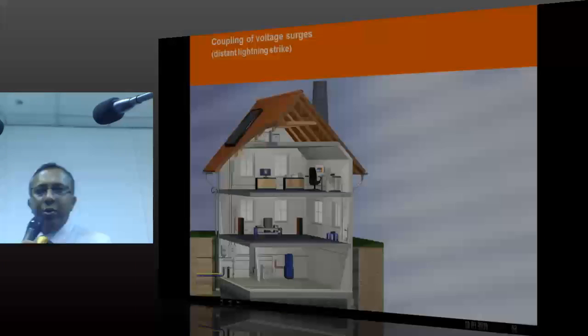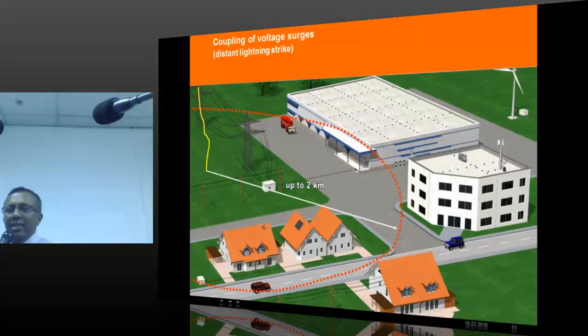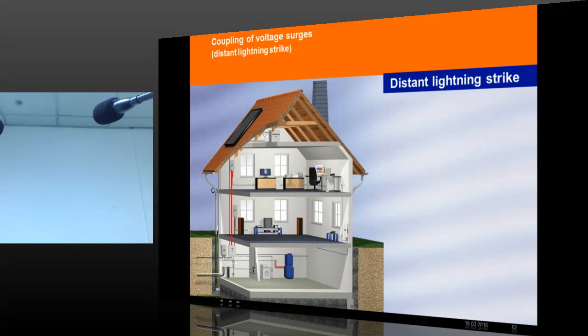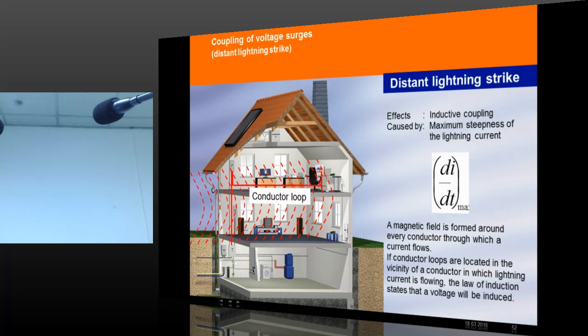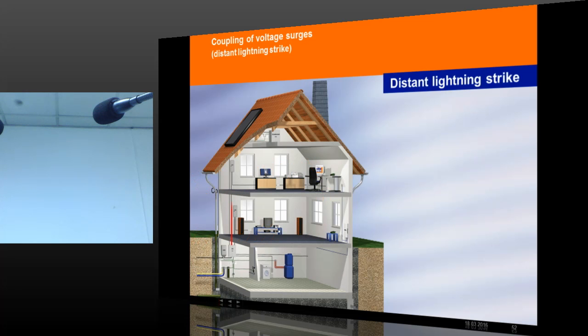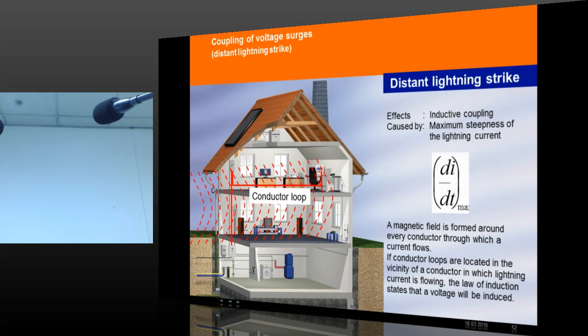What is important for you is coupling voltage in a distant lightning strike. See here you can see a building with a lightning strike approximately 2 kilometers away. What will happen to this particular wiring conductor loop due to the electromagnetic effects of lightning? Once the electromagnetic force flows through air, it will induce surges in the conductor loop. This is a conductor loop from the main distribution board, the wire going to some distribution board and finally to the computer. There can be surges induced in this wire which will destroy the computer.